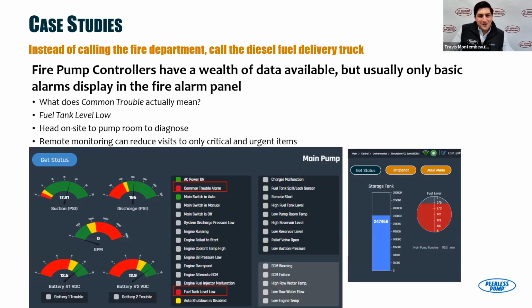Two more. We call this one, instead of calling the fire department, call the diesel fuel delivery truck. This all comes back to, what does your common trouble or system trouble alarm mean? Because that's what you get through your fire alarm panel, your remote alarm panel, through your BMS system or central monitoring. 2 a.m., fire site leader, you get a call: boss, common trouble alarm, what do I do? Either go on site, see what's driving it, look at the control panel, and then make a decision. Or if you have FireConnect, you roll over, say, hang on, let me call you back, and you get on your phone and look in the app and see, okay, there's a common trouble alarm, but I also have a fuel tank level low alarm. That's what's driving the common trouble, so it's not critical. I don't need to go on site right this second.